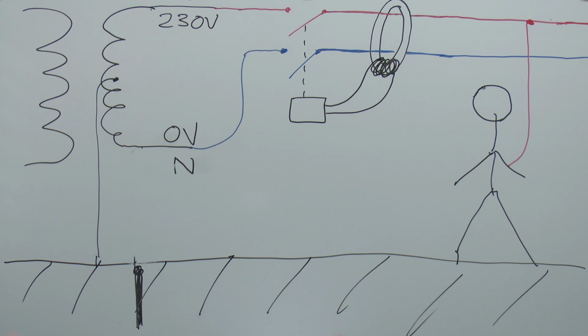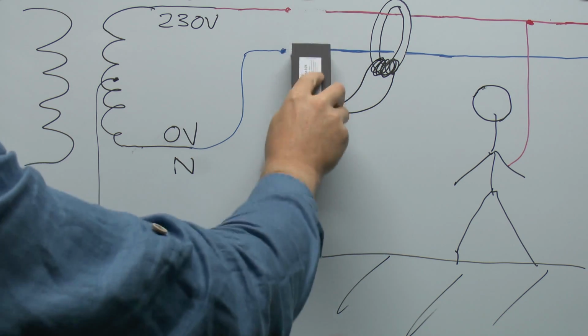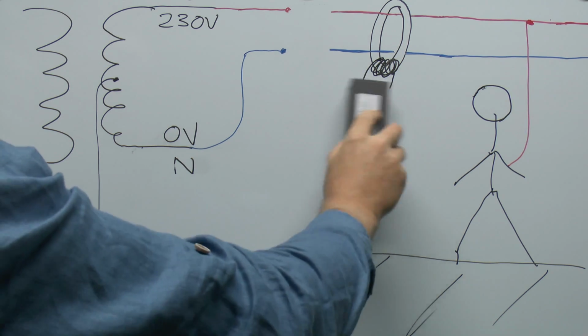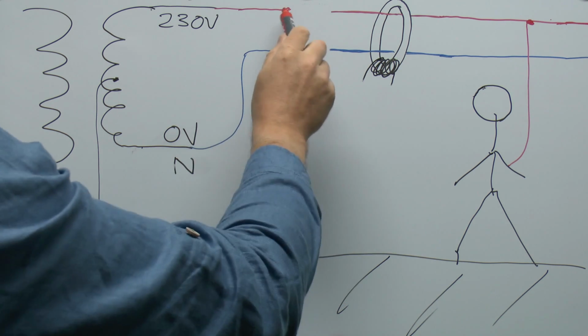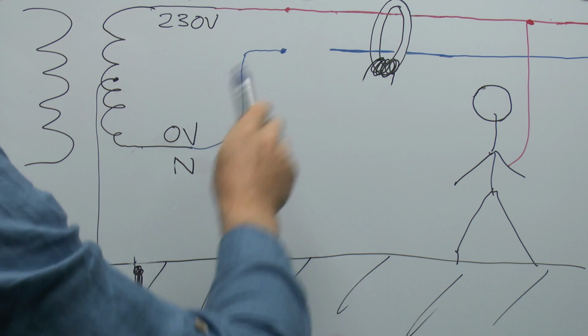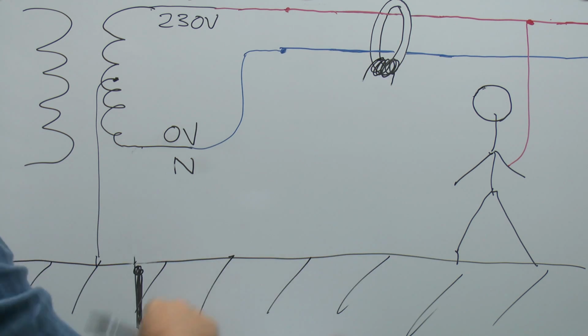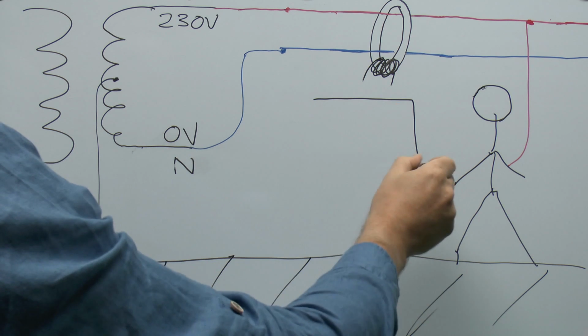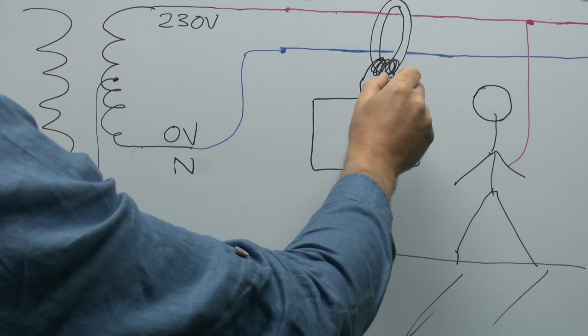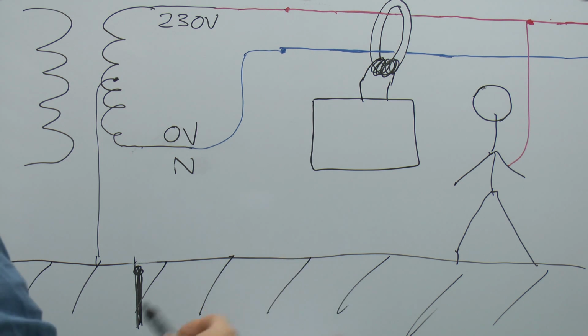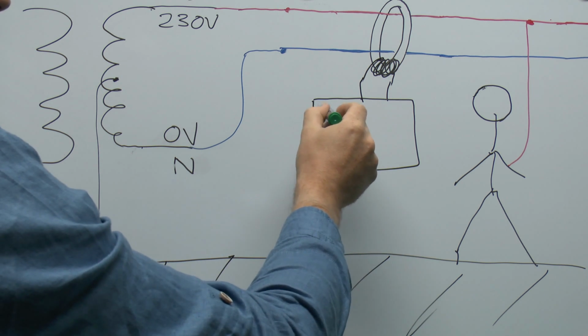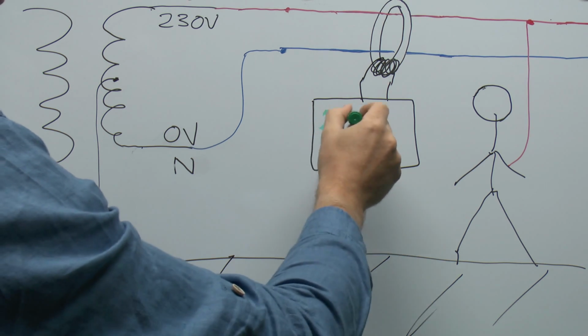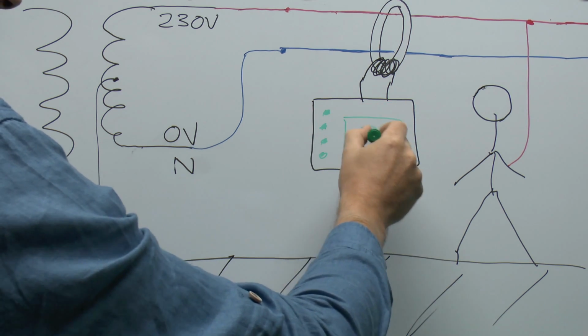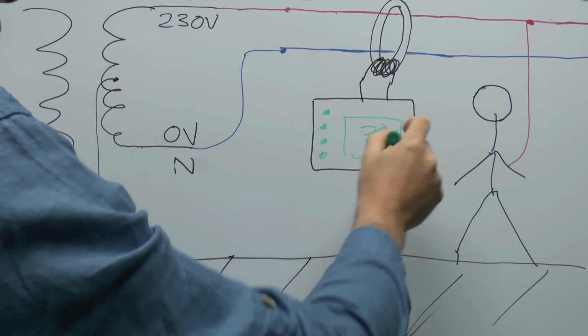Now, as well as RCDs like this, which will trip the supply when the current imbalance reaches a predefined level, there are some other devices which are essentially the same inside, but they don't contain a disconnection or a switch at all. Essentially the wires are just coming straight through the coil, and in this case the sense coil will be connected to some kind of monitoring device, generally with electronics in it, and typically that would have various indicators or warning lamps upon it, and possibly some sort of display which would display the actual leakage current instead.